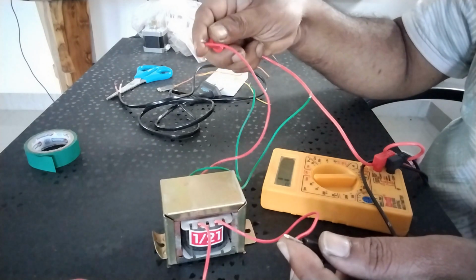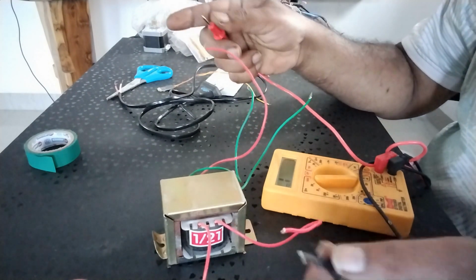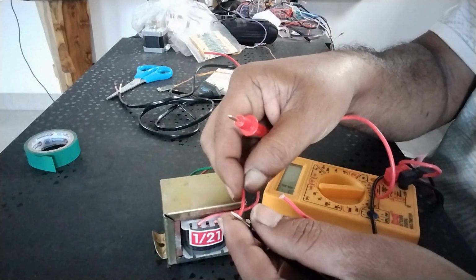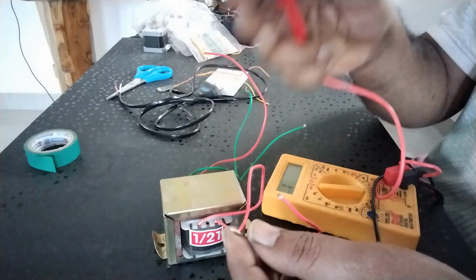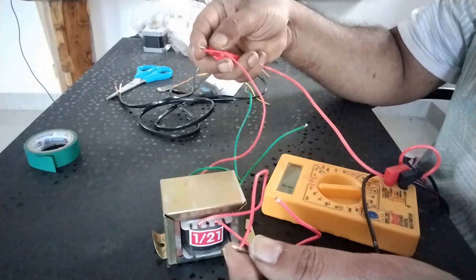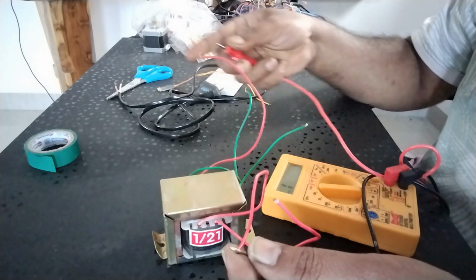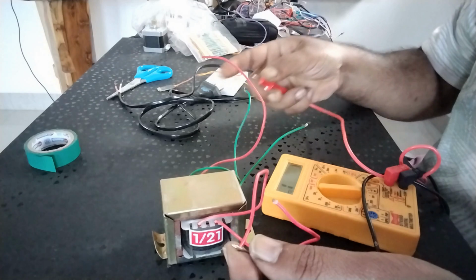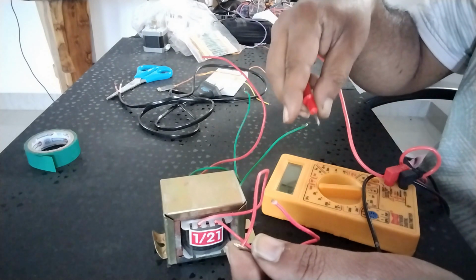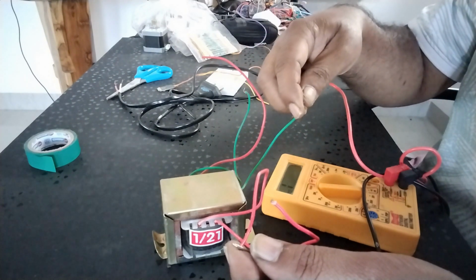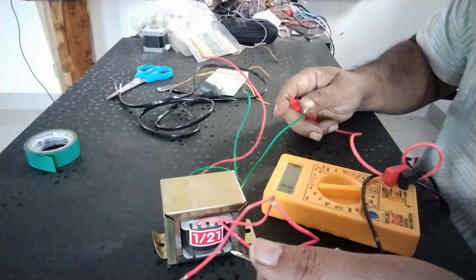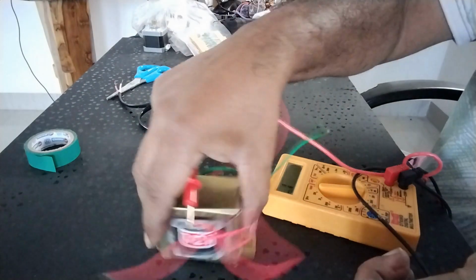Check for short circuits between windings, to ensure there is no short circuit between the primary and secondary windings. Connect one probe of the multimeter to one terminal of the primary winding and the other probe to any terminal of the secondary winding. If the multimeter does not beep, the windings are properly isolated and the transformer is safe to use. If you hear a beep, it means there is a short circuit between the windings, which makes the transformer unsafe for operation. Safety notes.